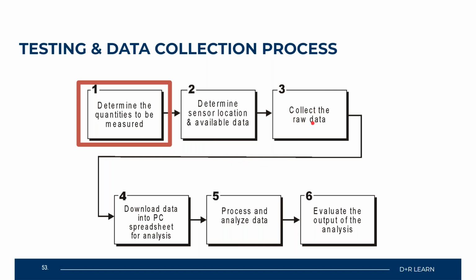Now, step 3, collect the raw data. During this phase, you've got data loggers that will be utilized to collect and store that raw data that is picked up by the sensors. The information collected by the sensors is not readily readable, so these data loggers are going to be utilized to collect and store that data. And one thing about the data loggers is that they run continuously and transfer that information to a database or some sort of a PC for analysis in the near future, when a technician needs to do any type of diagnosis or evaluation of a system.